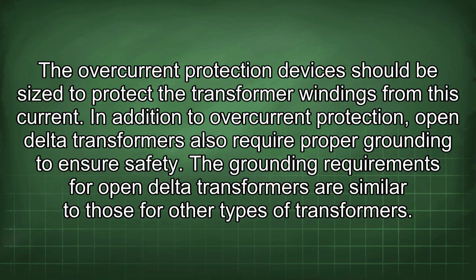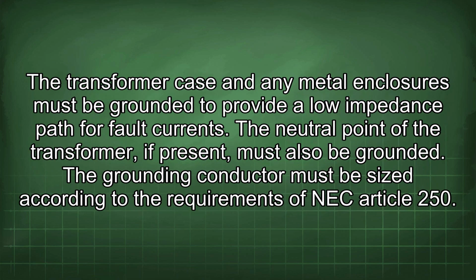In addition to overcurrent protection, open delta transformers also require proper grounding to ensure safety. The grounding requirements for open delta transformers are similar to those for other types of transformers. The transformer case and any metal enclosures must be grounded to provide a low impedance path for fault currents. The neutral point of the transformer, if present, must also be grounded. The grounding conductor must be sized according to the requirements of NEC Article 250.